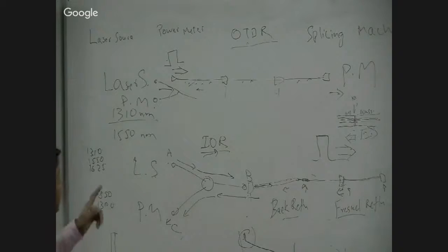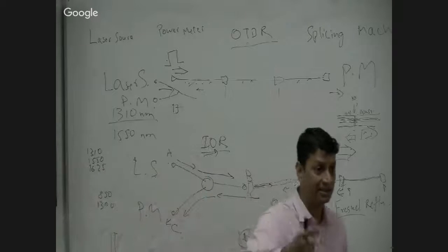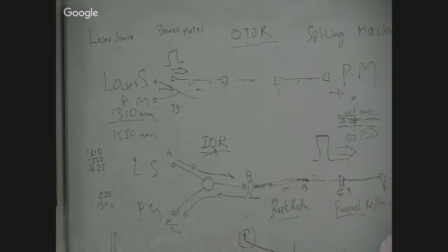So you should have an idea of where the far end of this cable is. Everything should be numbered and identified, so you should have a tag on it showing where that cable is going at the far end. And always, an active fiber should never be looked at in the eye. Never direct it to the eyes. So you should be careful that the fiber is not active, that it is dark. These are safety things you need to take care of.